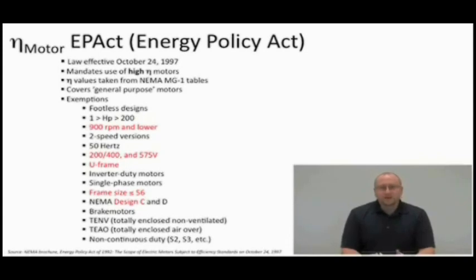Certain horsepower sizes, fractional horsepower sizes, are not considered to be using enough energy to make a difference, and greater than 200 horsepower motors are also not of a concern with this law, because as a motor gets bigger in size and design, the efficiency goes up. And once you get to a certain point, like 200 horsepower or greater, you really can't make them any more efficient. They're already efficient. So those are some of the exemptions that are in the EPAct.